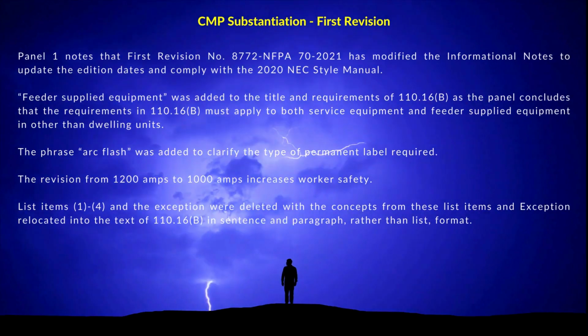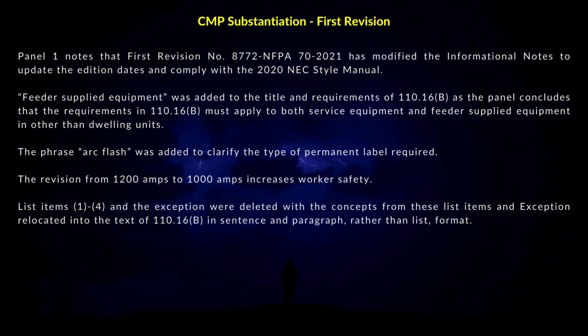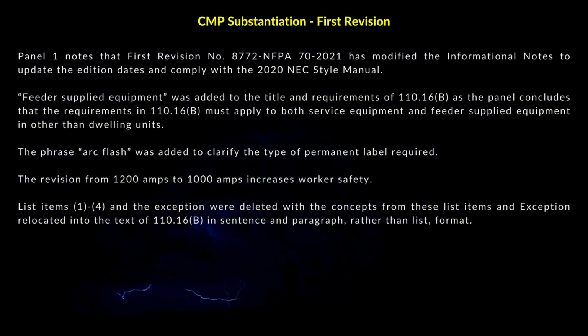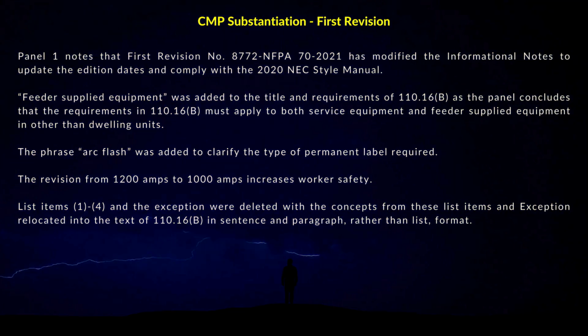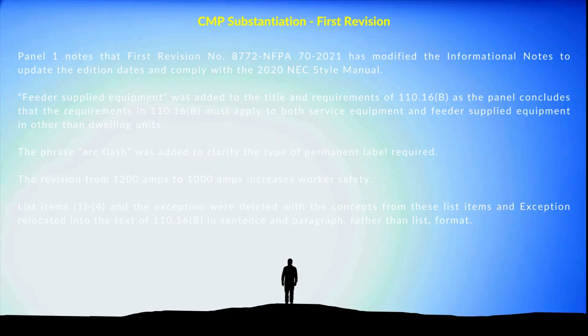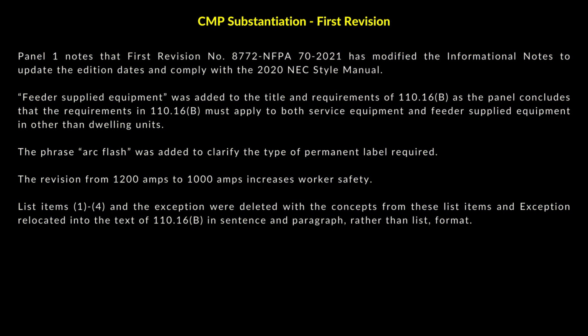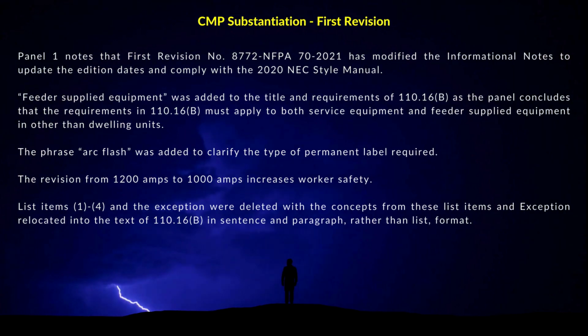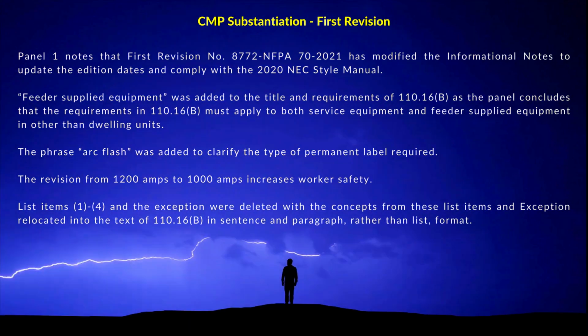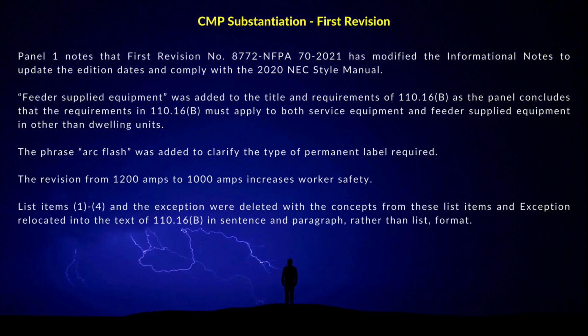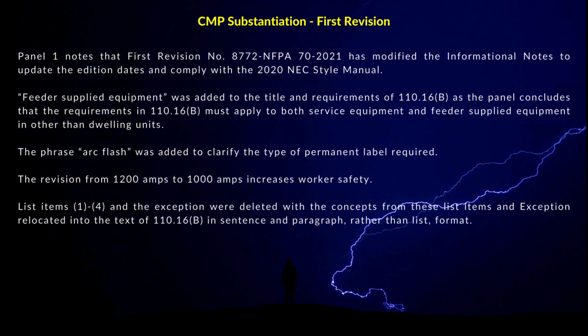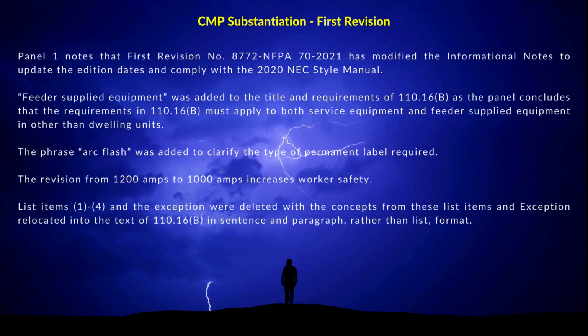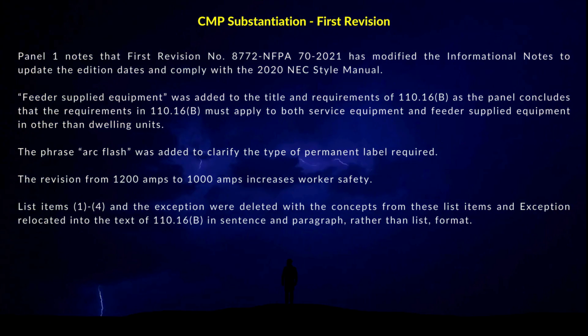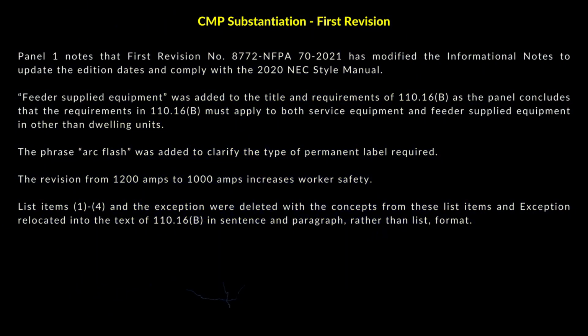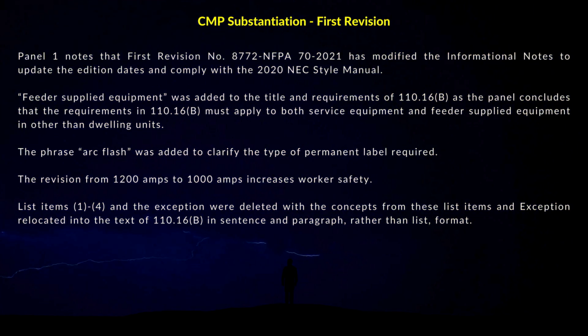Panel 1 notes that First Revision number 8772, NFPA 70, 2021, has modified the informational notes to update the edition dates and comply with the 2020 NEC Style Manual. Feeder supplied equipment was added to the title and requirements of 110.16(B), as the panel concludes that the requirements in 110.16(B) must apply to both service equipment and feeder supplied equipment in other than dwelling units. The phrase arc flash was added to clarify the type of permanent label required. The revision from 1200 amps to 1000 amps increases worker safety.